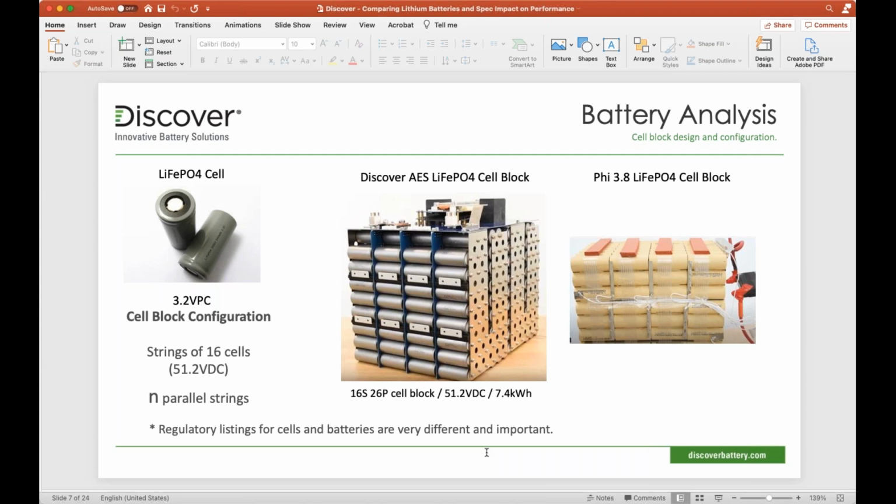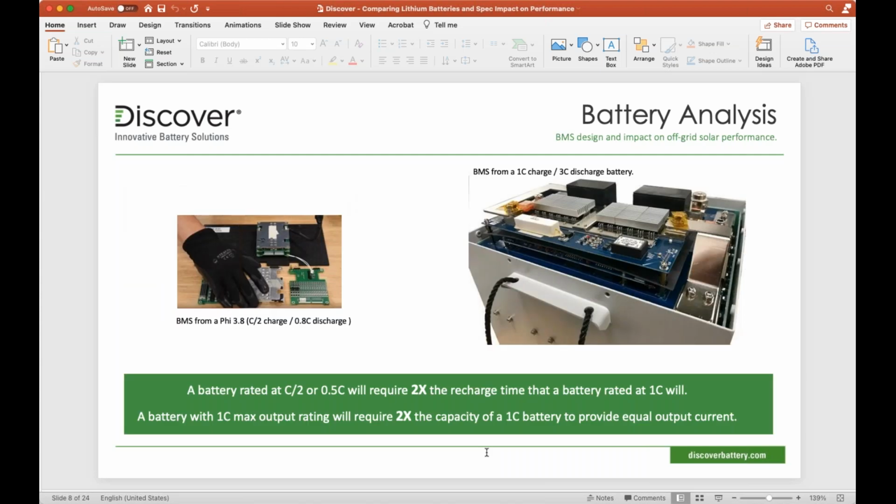Okay, when you go to the BMS design, which is the second piece, the BMS will sit on the cell block itself, and that BMS will manage all of the faults, warnings, temperature considerations, etc. of that given battery. They will oversee any of the cell balancing. Again, we've got hundreds of cells potentially in one of these batteries. They do need to be balanced, just like cells in a large lead acid string. When you're talking about 6 volt cells combined in 8s to make 48 volt, there is a balancing factor that goes on between all of those small cells. The BMS will handle and manage that.